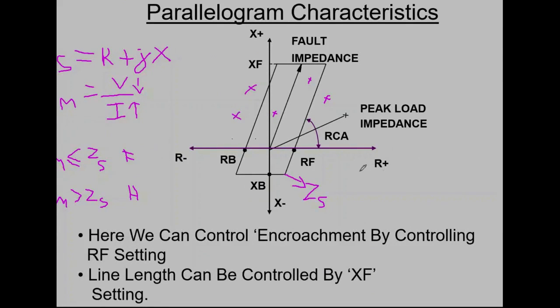Now what it does is, it will check this in a graphical way. Whenever it is plotting inside this graph, it's a fault. Whenever it is plotting outside, the system is healthy, because that's what we see here. The measured impedance is greater than the set impedance. That means it's outside. Yeah, here it is outside. Outside, outside, healthy. When it is on the line, that's why I have put one equal to symbol here. When it is exactly on the line, or it is inside, less than, then it is a fault.